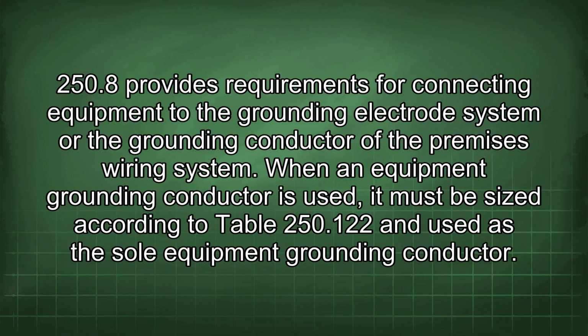250.8 provides requirements for connecting equipment to the grounding electrode system or the grounding conductor of the premises wiring system. When an equipment grounding conductor is used, it must be sized according to Table 250.122 and used as the sole equipment grounding conductor.